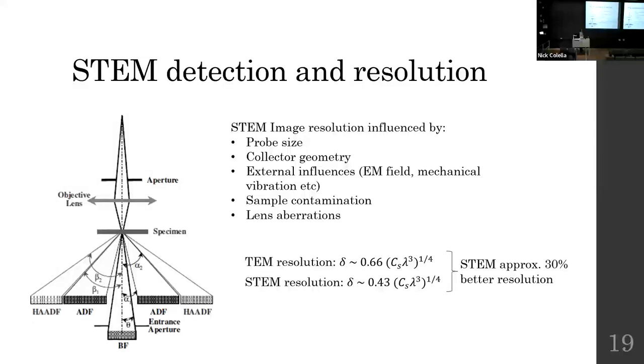Okay, so how do we detect the signal would be a good question to ask. And traditionally, what we do is we have a series of either ADF, which are annular dark field detectors, or bright field detectors. So the beam is coming down through the sample. We've already said it can be elastically scattered out at different angles.